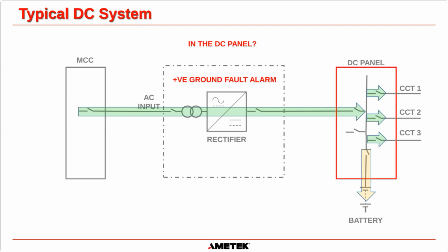Okay, now this is where it gets tough, because it could theoretically be in the DC panel. So we've worked out it's not in the battery, we've worked out it's not in the cable. So the only way we can isolate it to say, okay, is it in the DC panel, is to switch off all of your load circuits, okay? I do understand, in most circumstances, you're not going to get permission to do that. You're going to need a plant outage to do that. But it is the easiest way to do it. So basically, if there are only three circuits connected on this DC panel and you switch every one of those off, basically you are disconnecting anything from the outside world getting back into the DC panel.